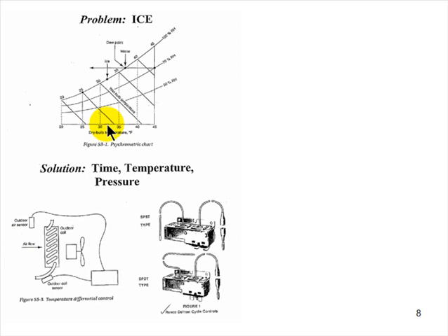At about 40 degrees outdoor temperature, that coil's 30, maybe even 25 degrees. It varies depending on the area too, but right around 35 to 55, definitely 40 degrees up to about 50, maybe even 55 degrees is when most defrost is going to happen. When it gets really cold, there's no moisture in the air to condense on the coil, so it's not an issue, unless you happen to get a rainstorm, which would then be an ice storm. So that's the most commonly occurring time to have defrost, 40, 45, maybe even 50 degrees, because at any of those temperatures, this coil is going to be at or below freezing.